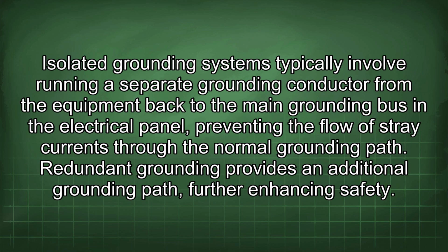Isolated grounding systems typically involve running a separate grounding conductor from the equipment back to the main grounding bus in the electrical panel, preventing the flow of stray currents through the normal grounding path. Redundant grounding provides an additional grounding path, further enhancing safety.